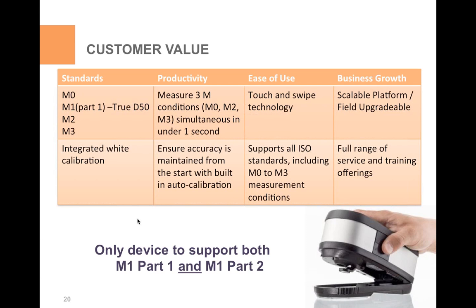Another thing to create efficiencies in the press room: many of you have been using them, have tried to, sometimes have lost the calibration tile. But if you notice in that illustration, underneath where the eye would be, there's a little plaque. It has a built-in auto calibration feature in the Exact. If it's sitting in the cradle, it can do an auto calibration. So that important step is always taken, and you won't ever lose the calibration because the white tile is actually built into the device.